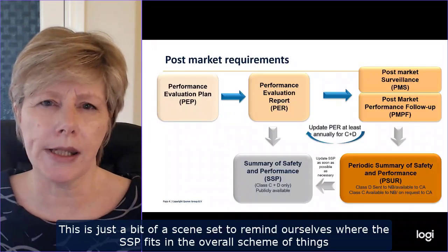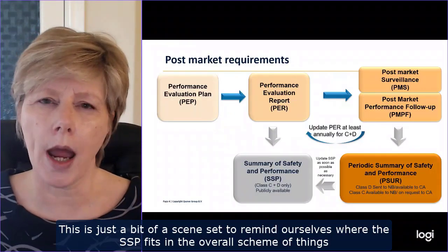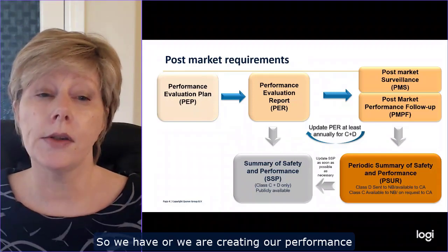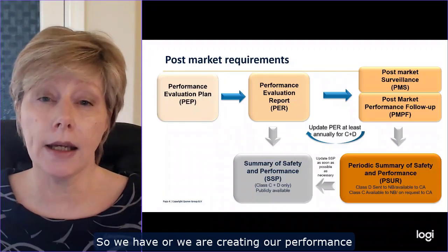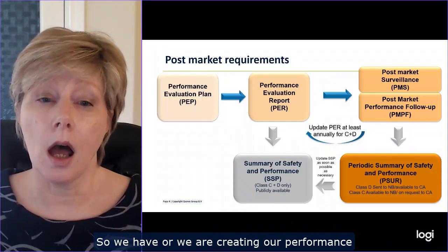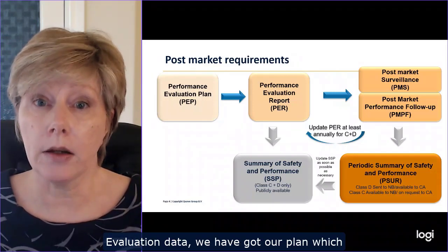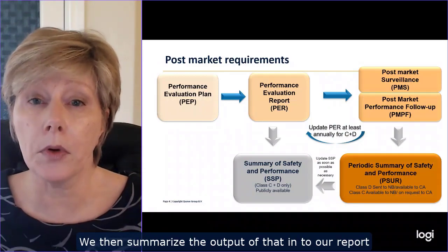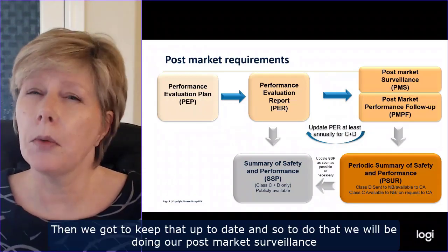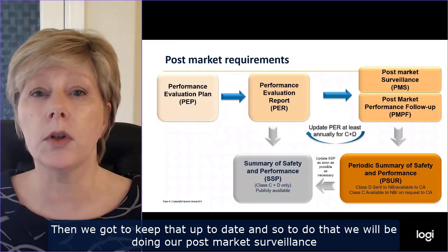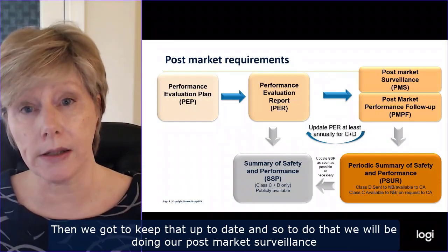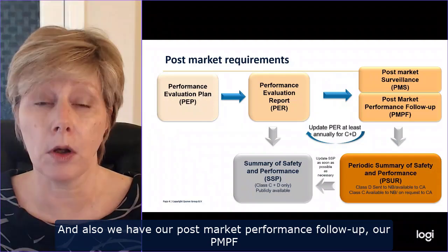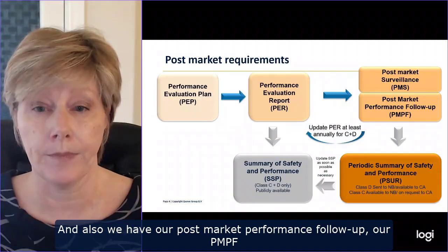So this is just a bit of a scene setter to remind ourselves where the SSP fits in the overall scheme of things. We're creating our performance evaluation data. We've got our plan, which we then summarize the output of into our report. Then we've got to keep that up to date. To do that, we'll be doing our post-market surveillance, and also our post-market performance follow-up, our PMPF.